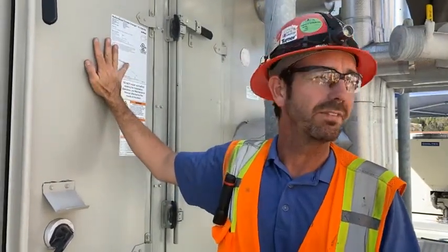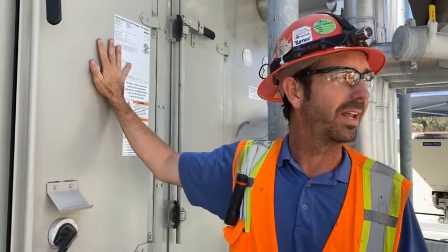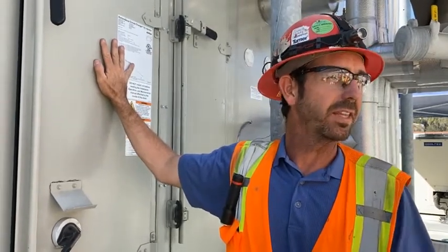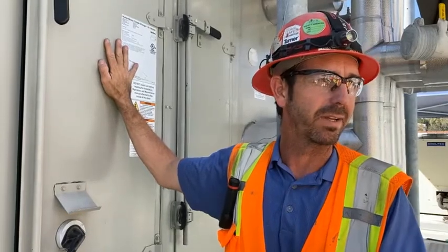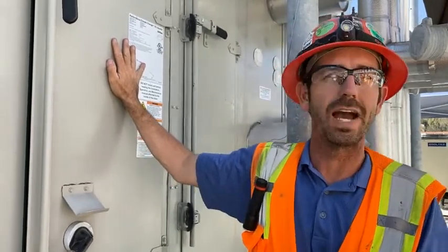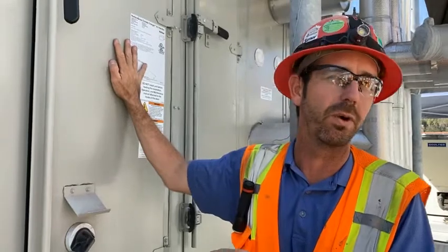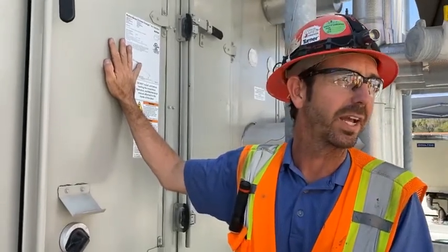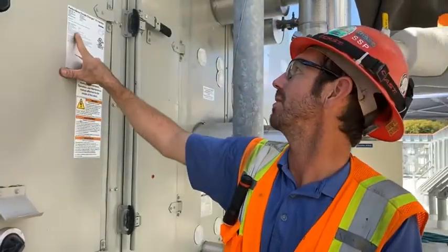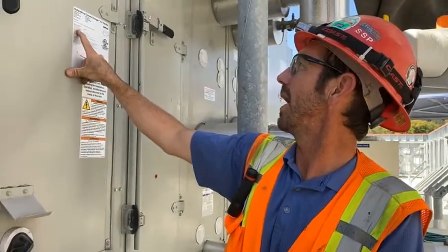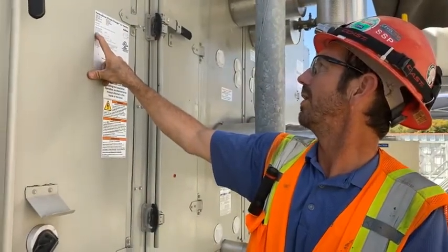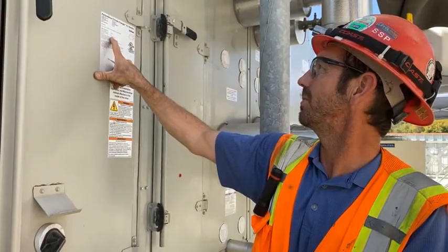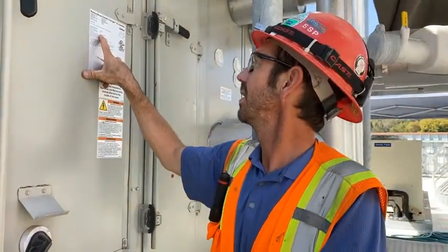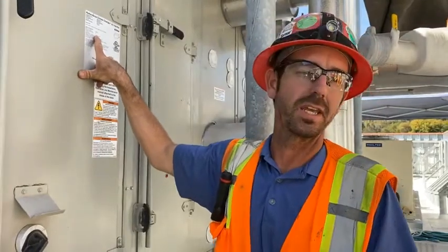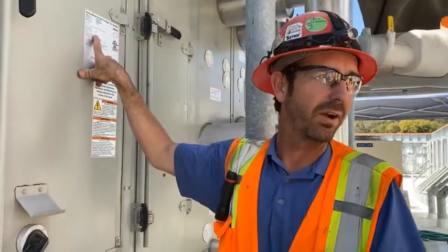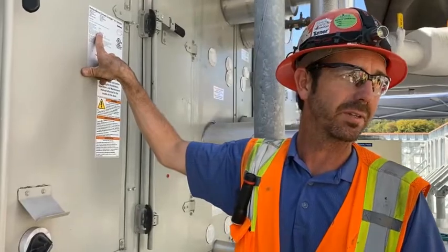So it's important too. I told the guys this morning in the other units, if you have an issue and you have to call like Danfoss tech support or something like that, be careful taking their advice on motor data programming. These units, again, if you ask for their support, they're going to tell you to program it for the motor horsepower and amperage and the FLA and all that, but it needs to be programmed for this up here. The maximum applied horsepower, which would be 14, and then the motor FLA right here, which would be 17.2 each. That's taking into consideration the higher horsepower of these specific style motors, okay?